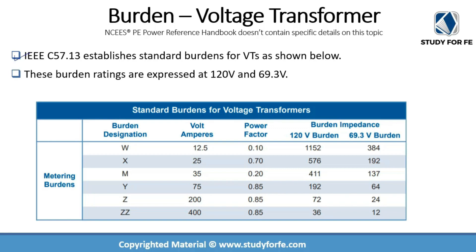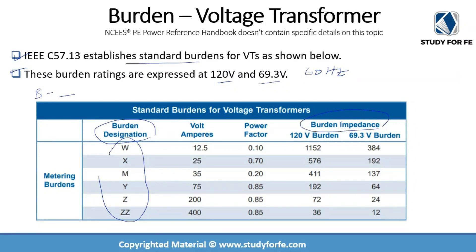IEEE standard C57.13 also establishes standard burden ratings for voltage transformers, shown in the table on this slide. These ratings are expressed for standard voltages of 120 volts and 69.3 volts at 60 hertz. The burden designation for voltage transformers is alphabetical, as opposed to the B-impedance format for CTs. For example, a VT with burden designation W has an impedance of 1,152 ohms, and burden designation M has a 69.3-volt burden rating of 137 ohms.